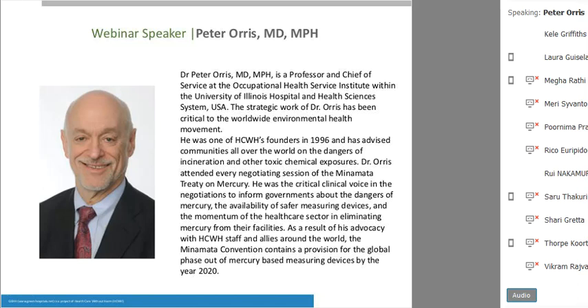Now, how to make this process safer, which is by definition not an enclosed process, because you must take the materials out of the sterilizer and put the materials into an aerator, is an industrial hygiene question. But I can tell you that through all of the changes that have been recommended for hospitals, with respect to changing the way that the sterilizers are constructed and exhausted, still they lose ethylene oxide into the atmosphere, and we don't know the lower levels.